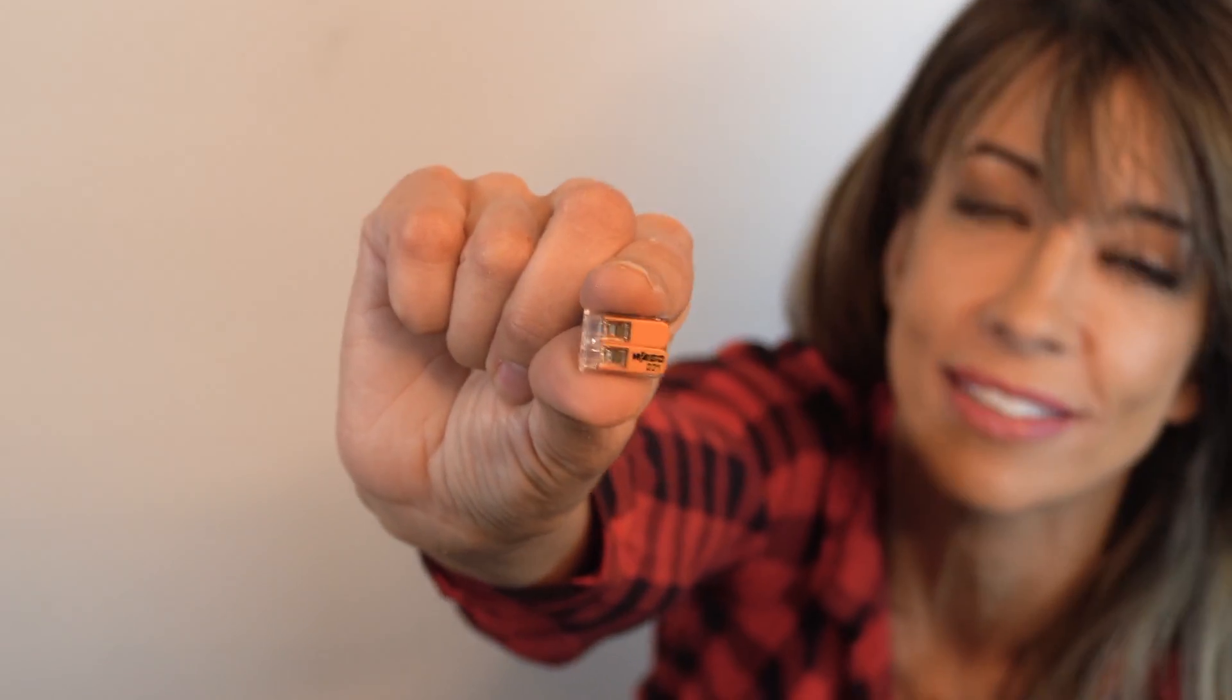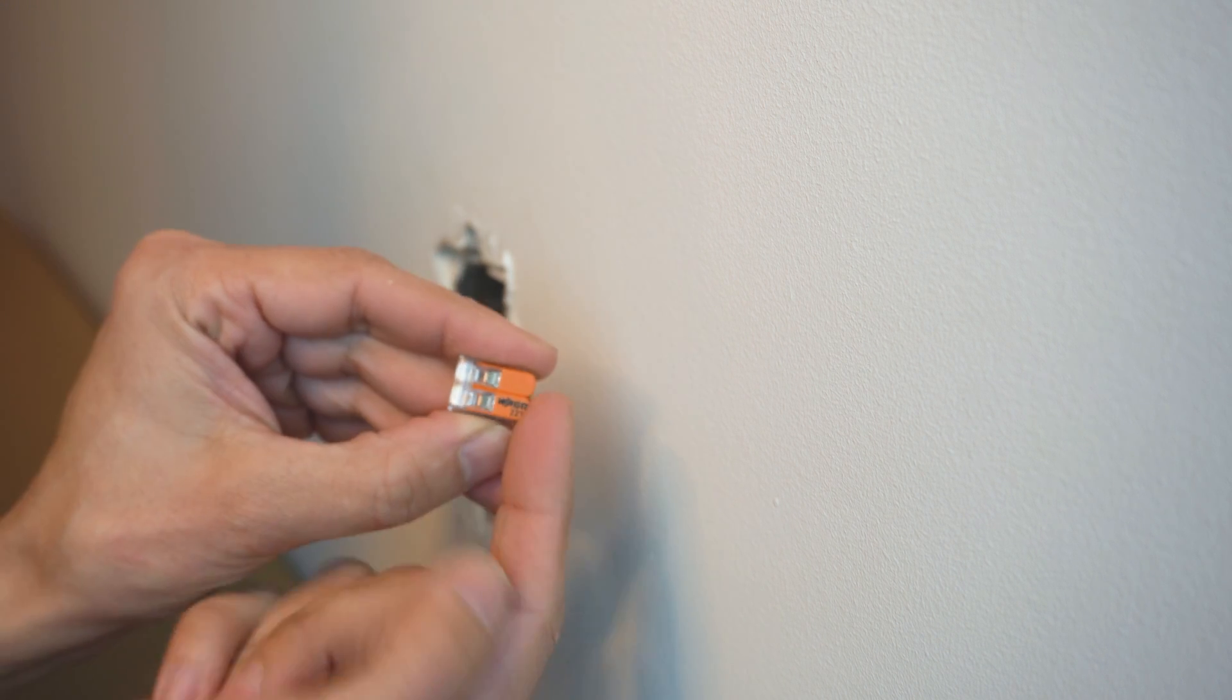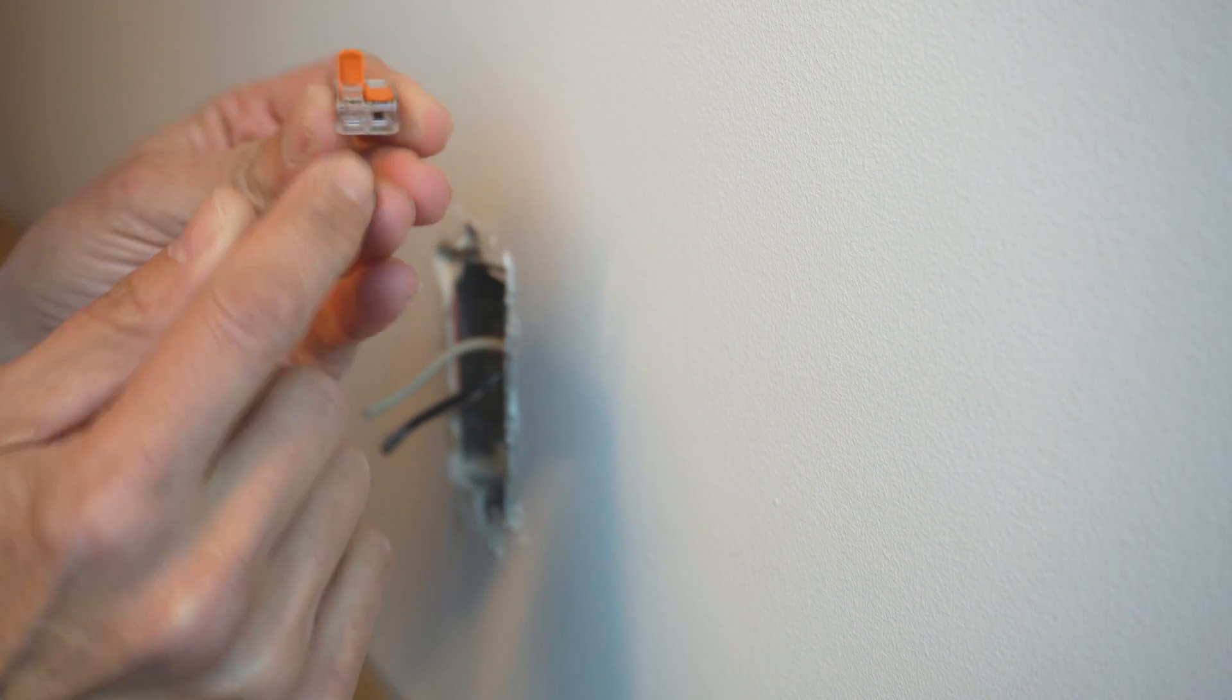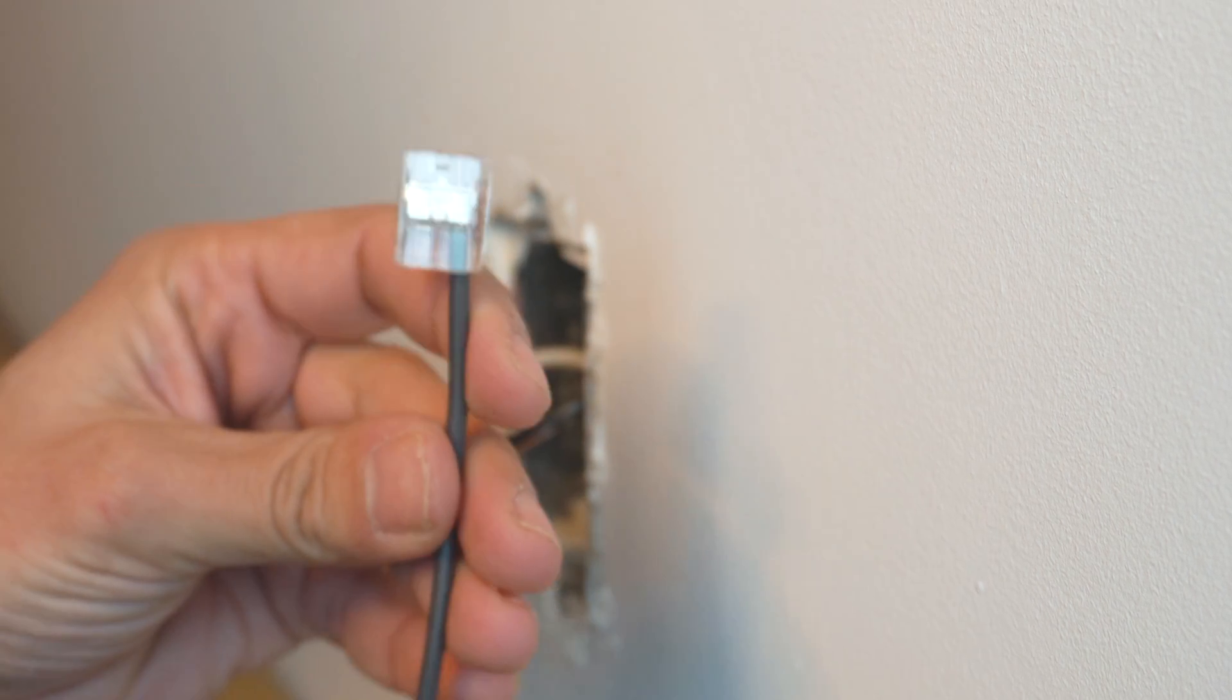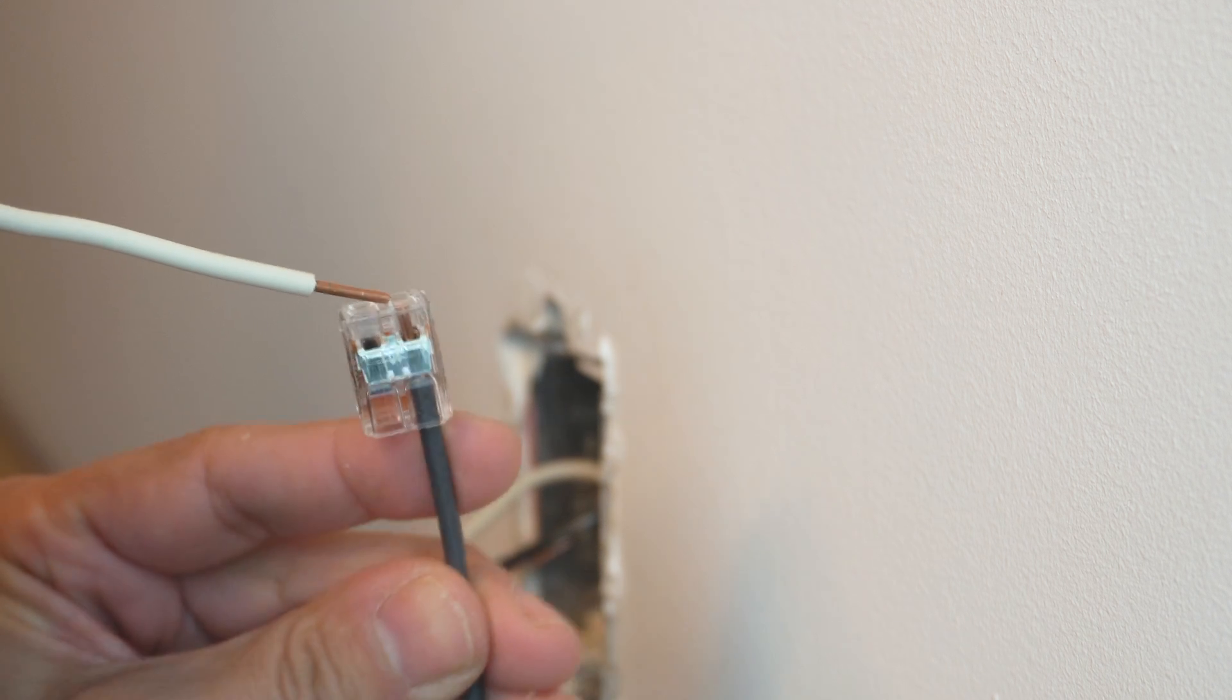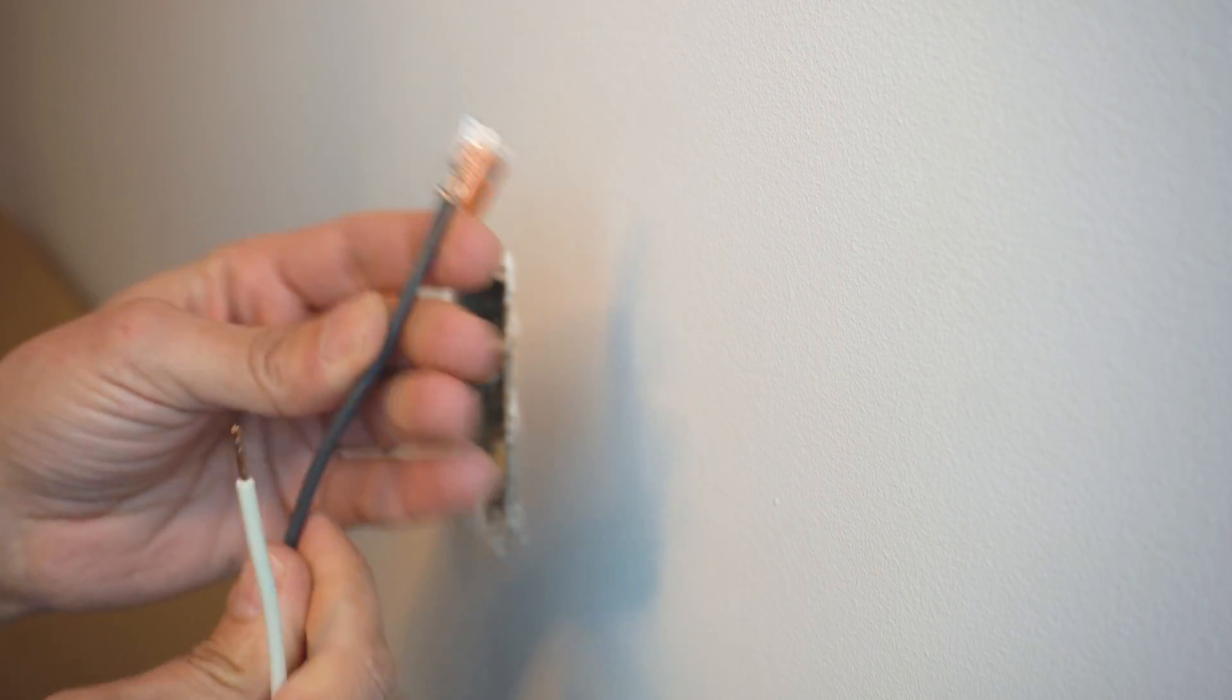And that takes us to method number two, which is the WAGO 221 lever connector. Now, by far, the most common way to connect your pigtails is to use your WAGO 221 lever connectors. How you use them is you open the lever like this, and it's going to open the port. You're going to take your wire and insert it. Now, there is a trick to using these. You're going to close the lever and take a look right here at the top of the lever connector. You're going to see that the housing is clear. And that is so you can visually confirm that your wire has gone all the way to the top so that you have made a safe connection on your pigtail.